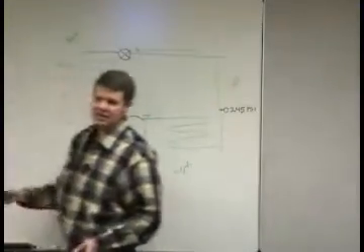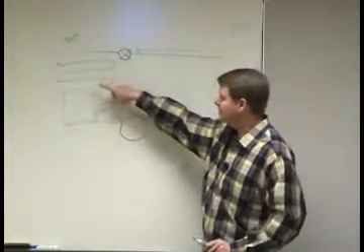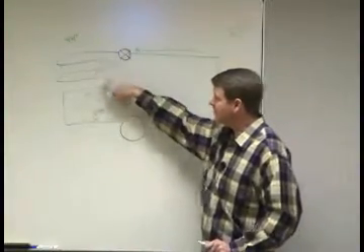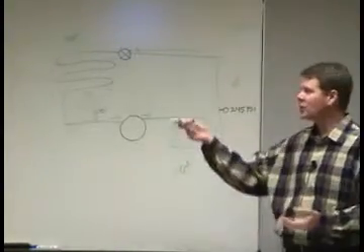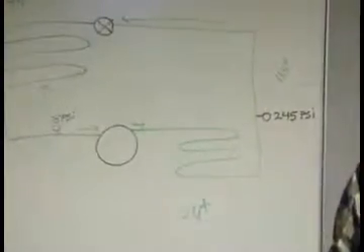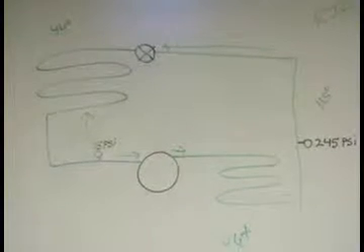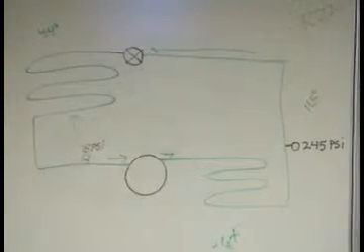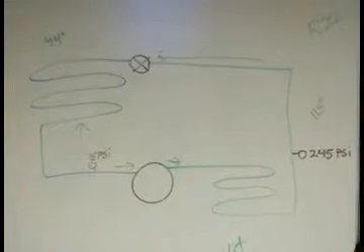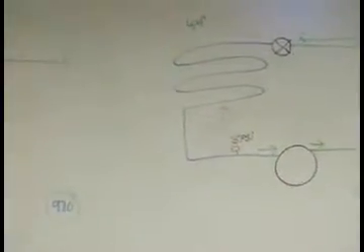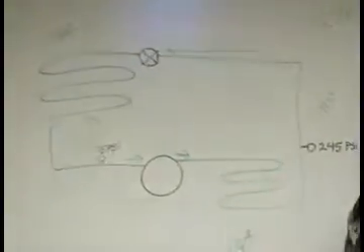So once again, we have taken all of this latent heat from that refrigerant and it gets absorbed into that refrigerant. We just added all that heat. Now the water takes 970 BTUs for a pound of water to change to steam. R22 is something different. I don't know how many BTU per pound it is to raise it. I didn't take the time to look it up, so don't quote me on 970, but the relationships are the same. You got to add a bunch of heat to that liquid to get it to boil off.